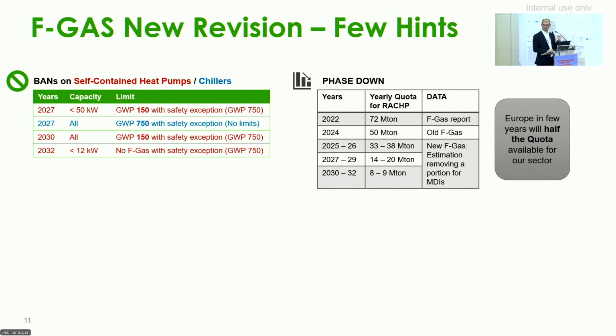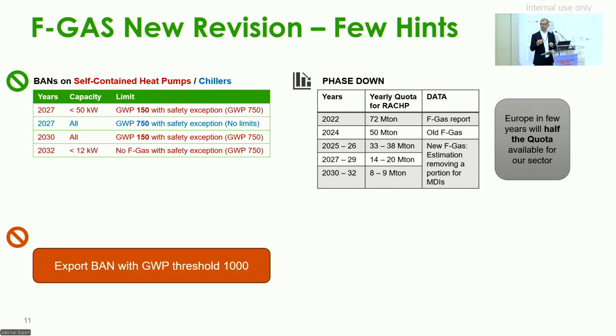This applies to the European Union, but why is it important also outside the European Union? First of all, because the same bans described in the upper table apply also to exported products with a GWP limit of 1,000. Second, because many manufacturers of chillers and heat pumps are located within the European Union and therefore affected by the limitations imposed. And third, because it will not be possible to ship units without refrigerants for the units to be filled locally. This will not be allowed.